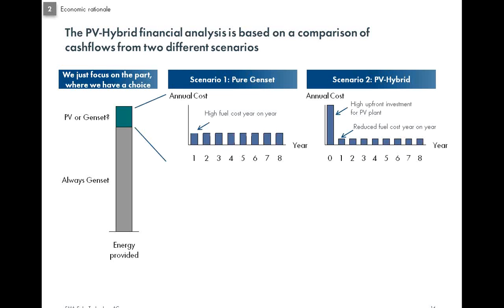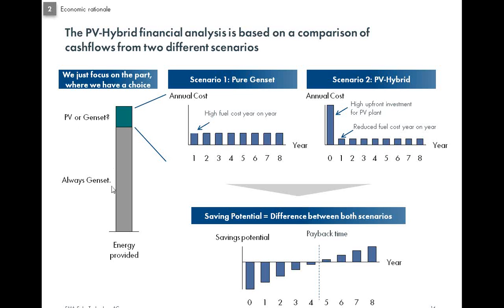All right. So now, what are the cost factors involved? As you can see, you have the gensets for which you've already paid the fixed cost, and then for the extra power, if you have a pure genset, then you'll have these fuel costs year over year. Whereas if you put in a PV diesel hybrid, then yes, you'll have high capex in the first year, but you'll have reduced fuel consumption year over year. And when you do the math and the comparison, you'll see that the payback time will come to around 4.5 years in this particular case. This is how the payback would come about.